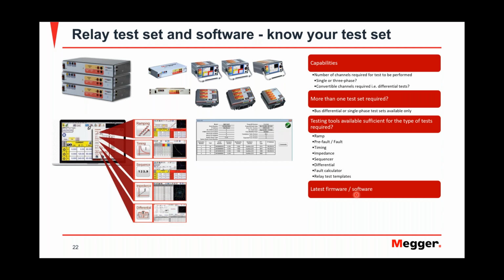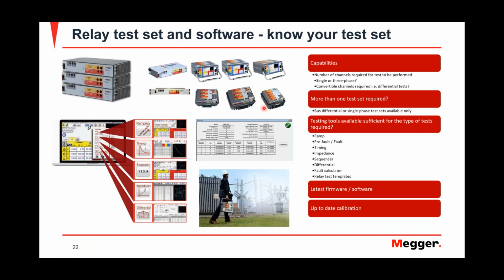Being on the manufacturing side of testing equipment, I could tell you a lot of the problems that are in the field could be solved by updating the firmware and the software. Having the latest firmware and software on the test equipment will solve a lot of the problems that you have. And make sure that you have up-to-date calibration on your equipment.